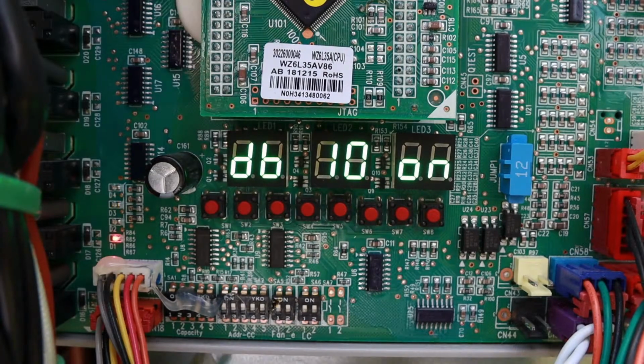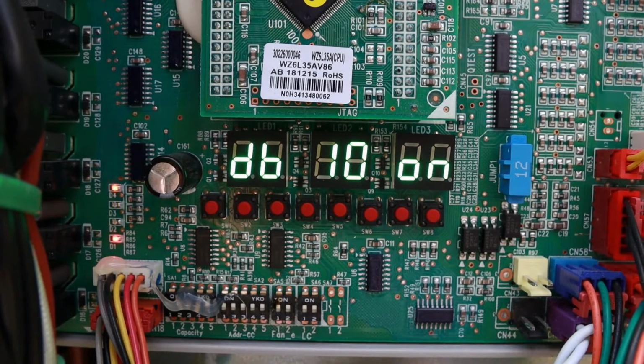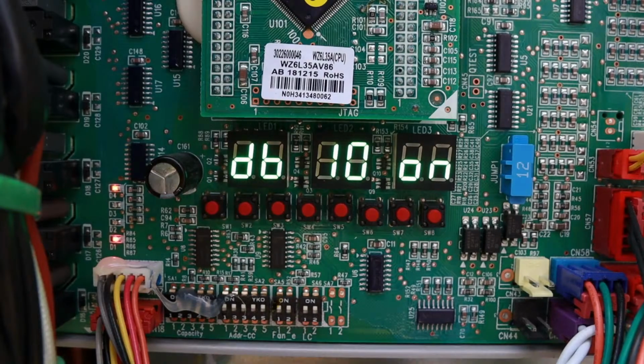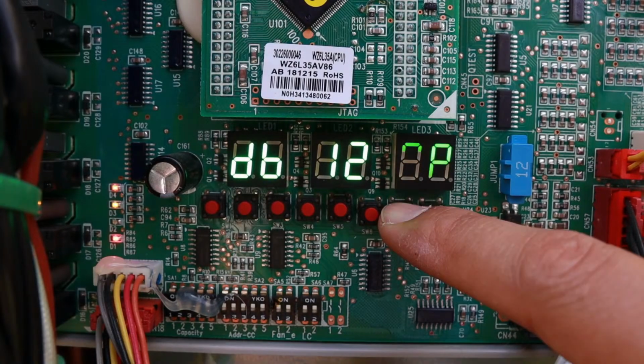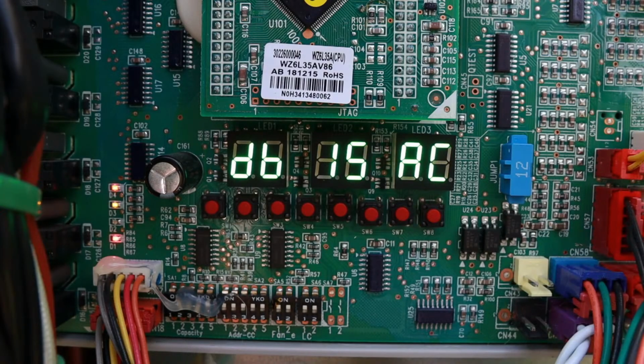So do that before you start the commissioning, and then when you get to step 10, just let the system run. It will take again about 5 minutes or so, and then you will see that the system will jump automatically to step 12. On step 12, the system is asking us to confirm that we're ready for the startup cycle. So in this step, we're going to go ahead and press SW7 to confirm. We're going to press it once, and then we'll see how it jumped automatically to step 15. Step 15 is the full startup cycle.